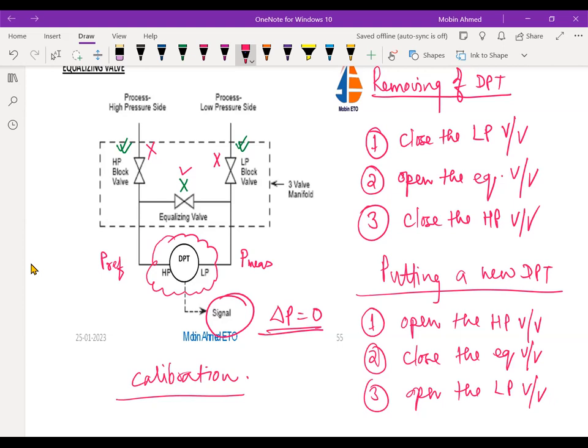Clear? Any doubt to anyone? I had a doubt. In the removing first step, when you said close the low pressure valve, right? Yeah. Right after that, before opening the equalizing valve, it won't damage the diaphragm? No, no, because you are not relieving the pressure. You have just closed the valve. Okay, okay. Got it. Okay.